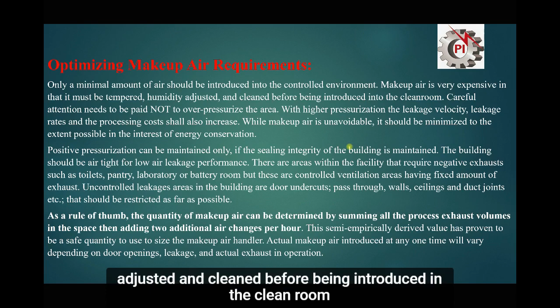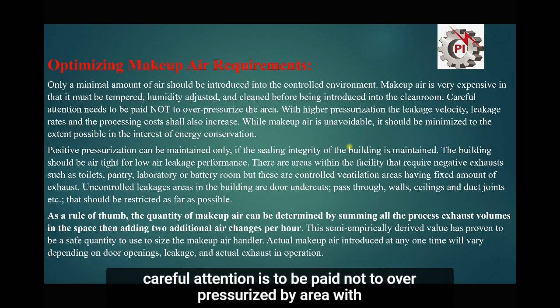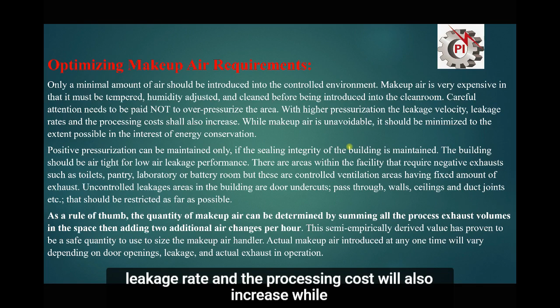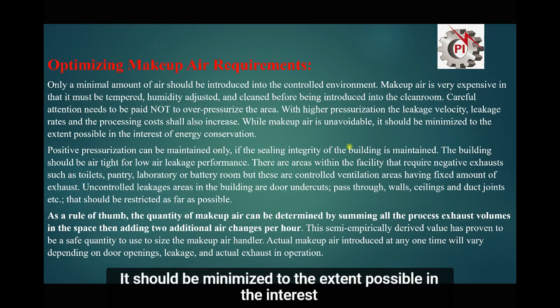Now we will discuss how the positive pressure is created. The makeup air requirement is the most important thing for creating the positive pressure in the clean room. Only a minimal amount of air should be introduced in the controlled environment. Makeup air is very expensive, as it must be tempered, humidity adjusted and cleaned before being introduced in the clean room. Careful attention needs to be paid not to over pressurize the area. With higher pressurization, the leakage velocity, leakage rate and the processing cost will also increase. While makeup air is unavoidable, it should be minimized to the extent possible in the interest of energy conservation.